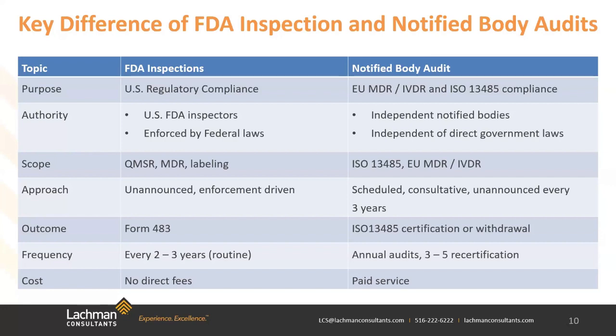The overall outcome of these can be different, but similar. FDA inspections result in an inspection report that you're provided. However, if there are deficiencies, FDA will provide you a Form 483 before they leave the inspection, listing out any observed deficiencies that they identified during the inspection. And then you would go ahead and respond to that 483 within 15 business days. Now, depending upon your response and your corrective actions, these could lead to higher enforcement, such as warning letters, fines, import alerts, product seizures, or injunctions, whereas a notified body audit results in the issuance of an audit report followed by a certification.